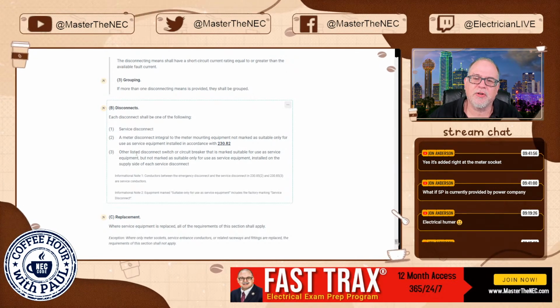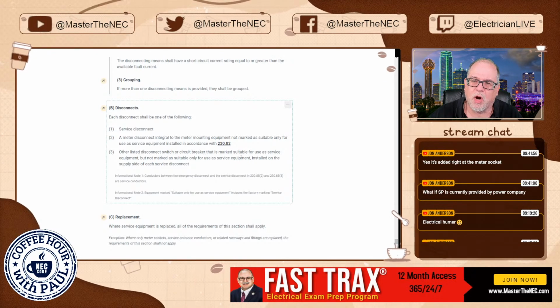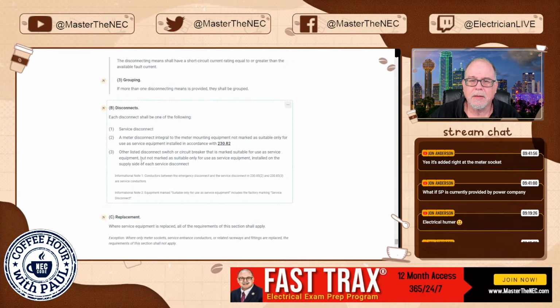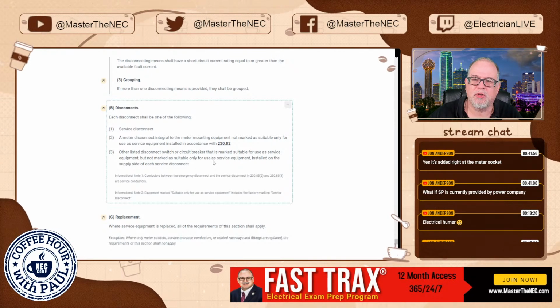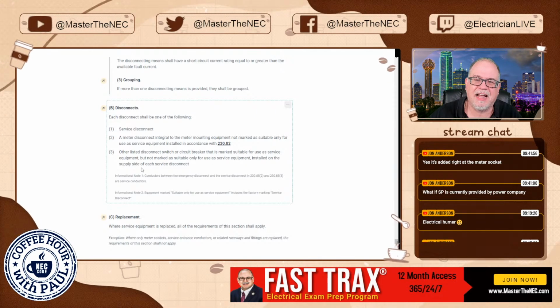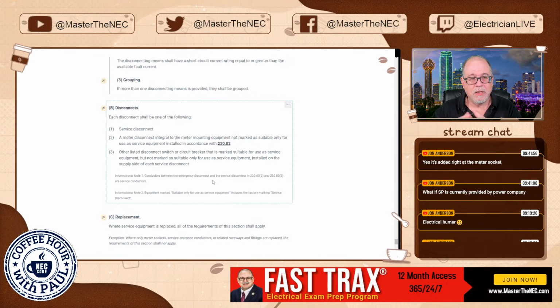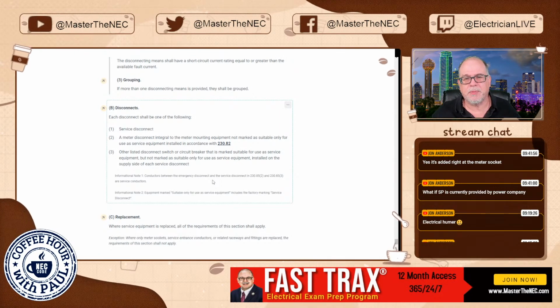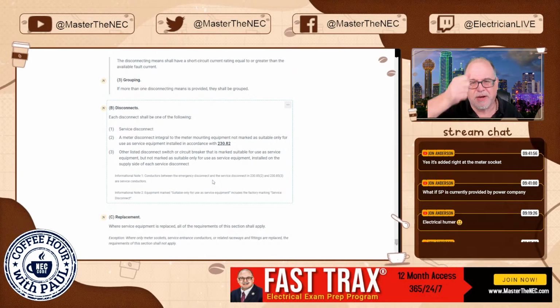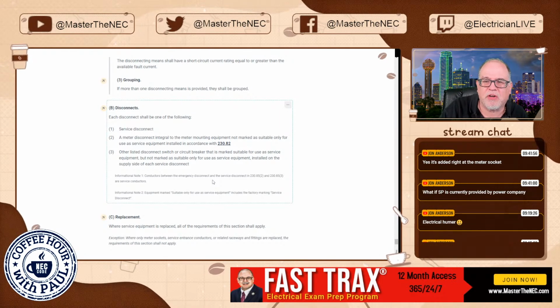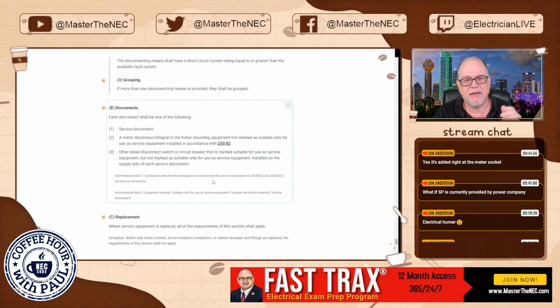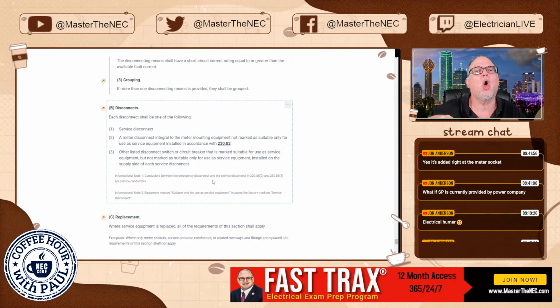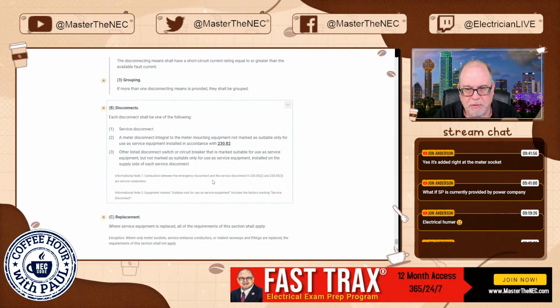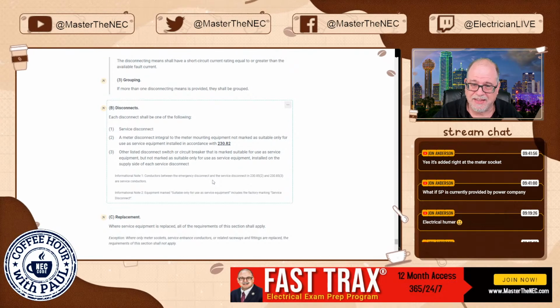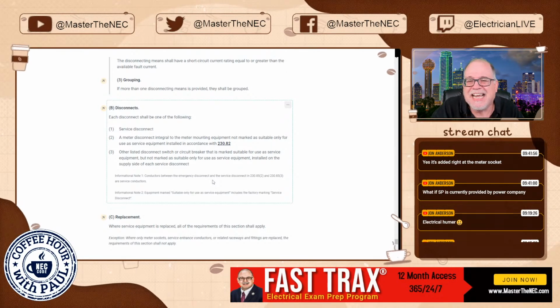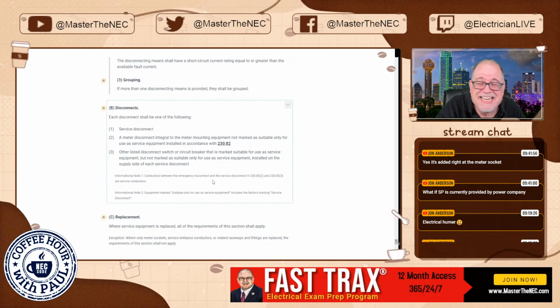And number 3 says other listed disconnect switch or circuit breaker that is marked suitable for use as service equipment, so check those markings, but not marked as suitable only for use as service equipment installed on the supply side of each service disconnect. Okay, so this would be an example, let's say a 200 amp service. I could put a disconnect outside, just a circuit breaker, let's say, right? And it's got to be marked suitable for use as service equipment. Okay, sounds great, but not marked as suitable only, okay, only for use as service equipment. And as long as, again, it's installed on the supply side of a service disconnect. So what does that tell you? It is not the service disconnect. It is just a disconnect.